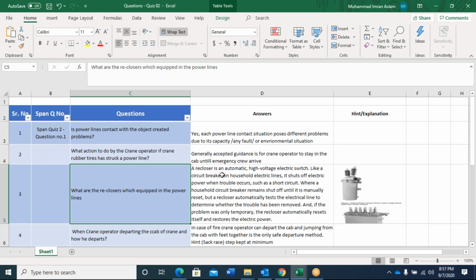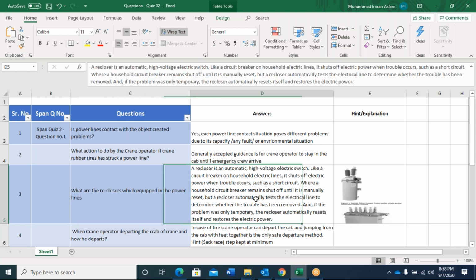The function of the reclosure is an automatic high voltage electrical switch, just like an automatic high voltage electric switch, like a circuit breaker. These reclosures test the electric lines to determine whether the trouble has been removed or not, repeating the test for 3 or 4 cycles to check whether the line is disconnected or the fault is removed. These reclosures test themselves and reset automatically. So that is the main function of these reclosures in a power line, which I already explained.